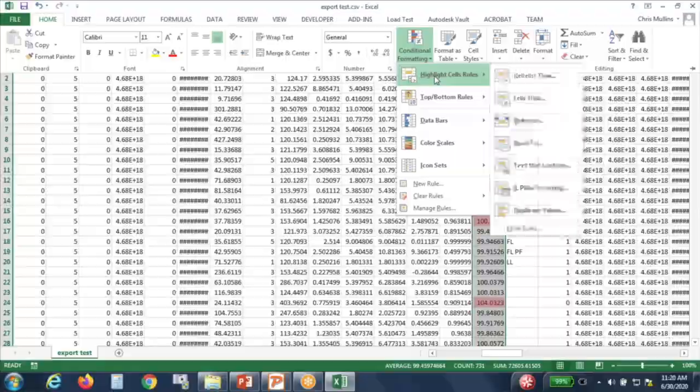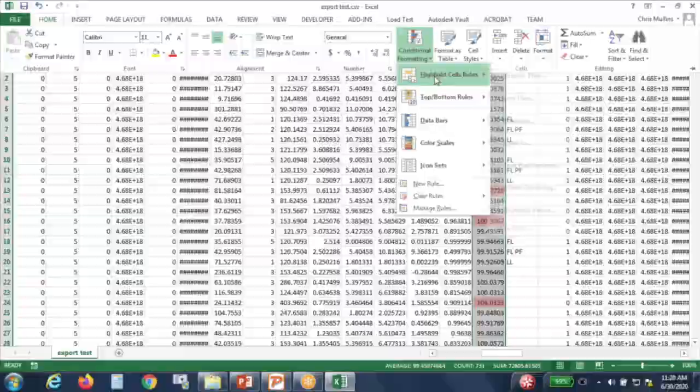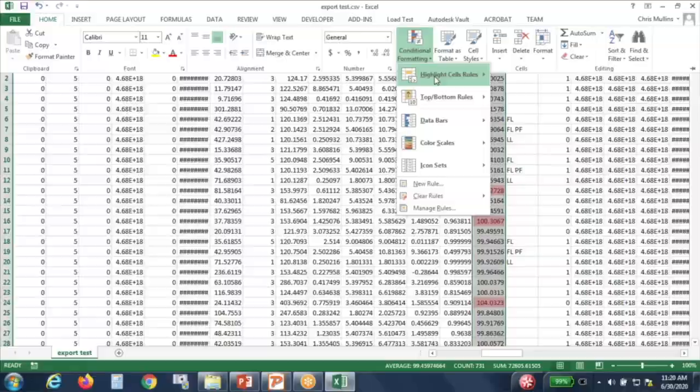But something like this is a light load, 0.8 average there. You can see right here, an average of 0.4 amps. That's a pretty lightly loaded site. Same thing here, just barely below that as well. So again, it gives you another tool you can look at, because if I've got a bad registration, let's look at this one, 90%.